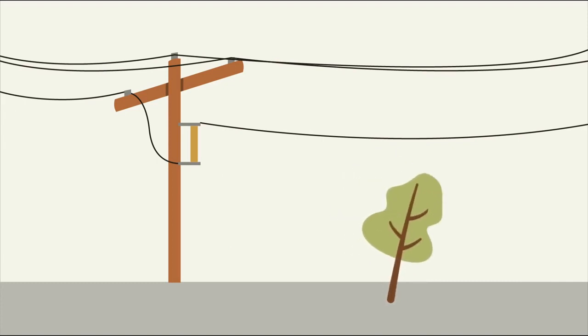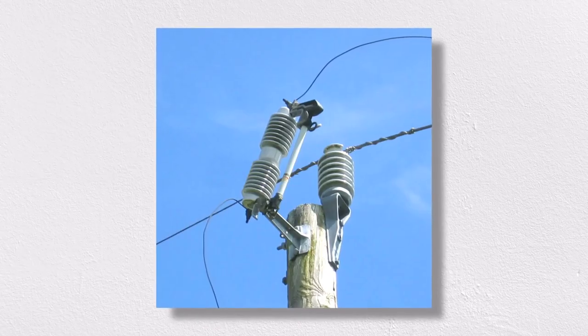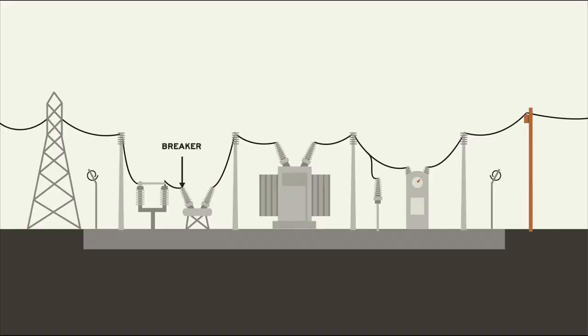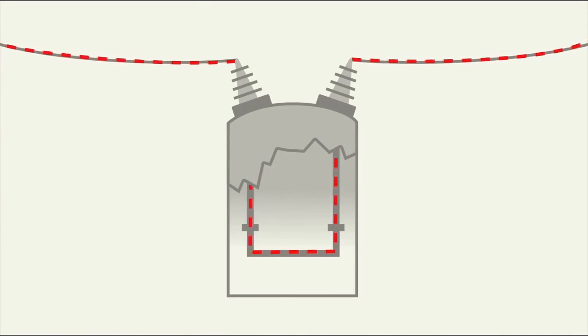One of the most common types of electrical fault is a short circuit to ground. This type of fault creates a low resistance path for current to flow and leads to an overload of power lines and equipment. The simplest way to protect against this type of fault is with a fuse, a device that physically burns out at a certain current threshold. Fuses are dead simple and don't require much maintenance, but they are one-time use and can't be used to interrupt current for other types of faults. Circuit breakers, on the other hand, serve similar roles as fuses but provide more sophistication for dealing with a wide variety of faults. Like disconnect switches, circuit breakers need to be carefully designed to interrupt huge voltages and currents without damage.